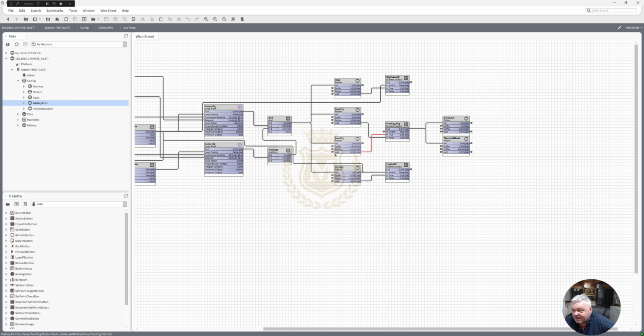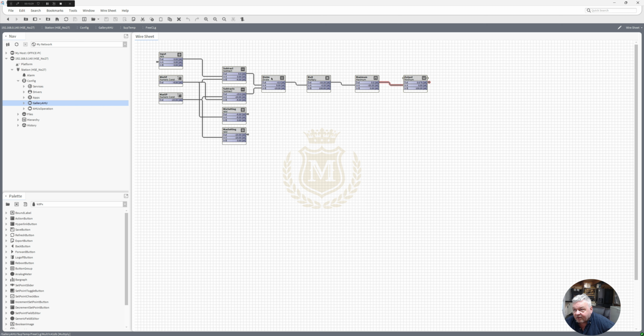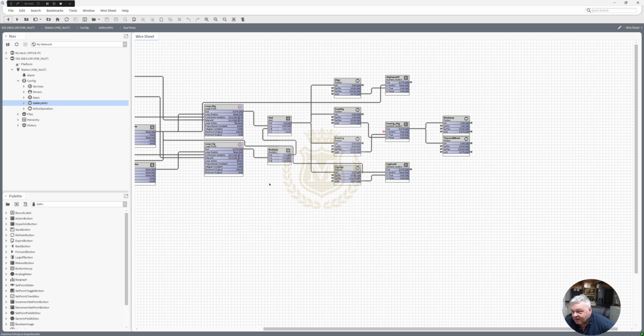And we've got in here another folder. There's my output of that folder, and we're subtracting here different calculations. So minimum set point -5, maximum set point -20. And if we follow it through, probably not making a good example here. It'd probably be better to see it in live working calculation. That's my loop heating and that's my loop cooling. Let me, which is coming out in B there, which is 0 at the moment, but if that was 100%, that would then be 100.